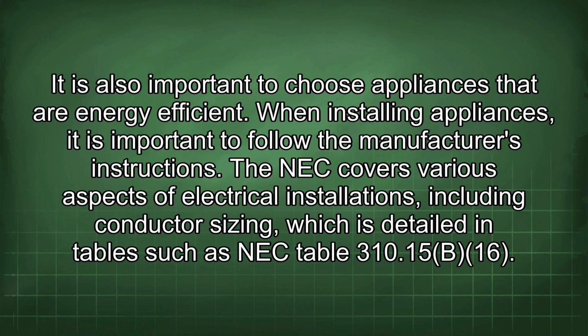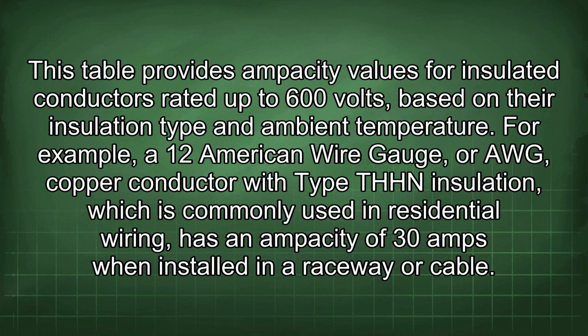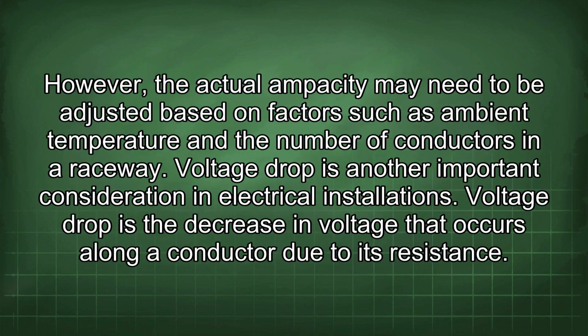The NEC covers various aspects of electrical installations, including conductor sizing, which is detailed in tables such as NEC Table 310.15(B)(16). This table provides ampacity values for insulated conductors rated up to 600 volts based on their insulation type and ambient temperature. For example, a 12 American wire gauge or AWG copper conductor with type THHN insulation, which is commonly used in residential wiring, has an ampacity of 30 amps when installed in a raceway or cable.